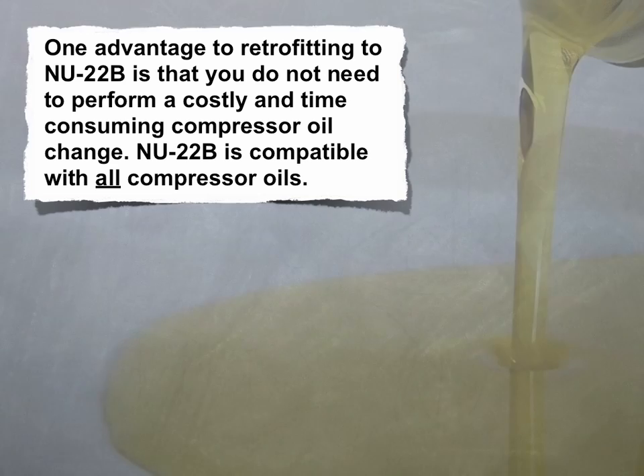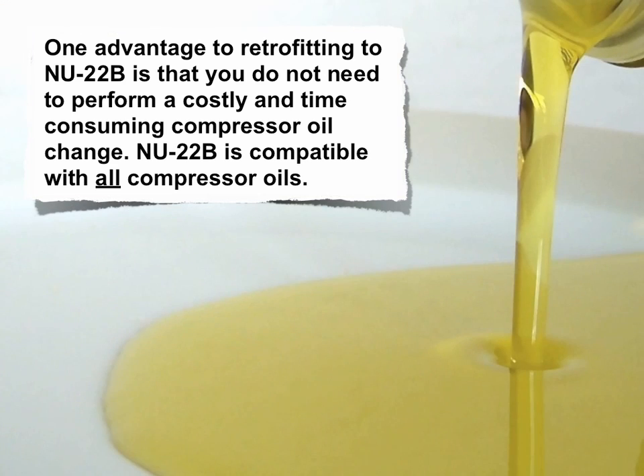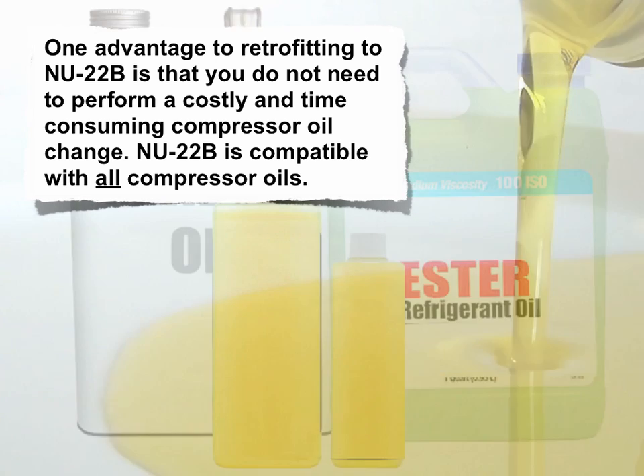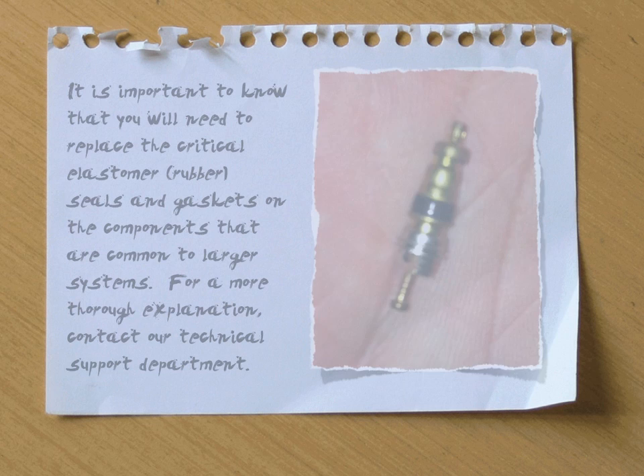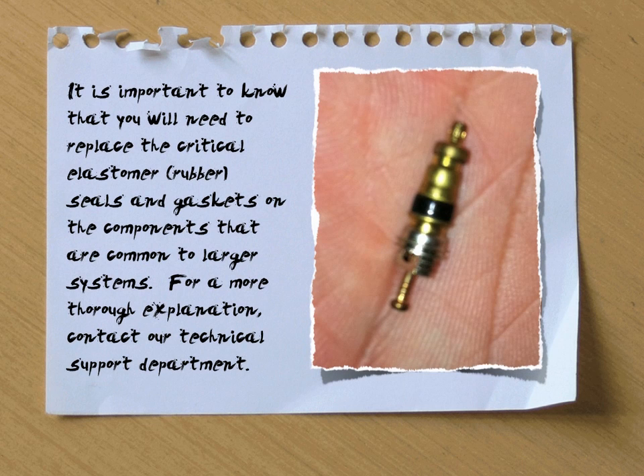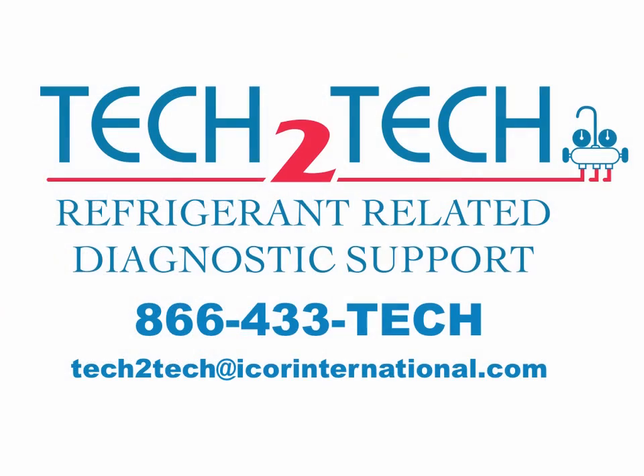One advantage to retrofitting to NU-22B is that you don't need to perform a costly and time-consuming compressor oil change. NU-22B is compatible with all compressor oils. It's important to know that you'll need to replace the critical elastomer rubber seals and gaskets on the components that are common to larger systems. For a more thorough explanation, contact our technical support department.